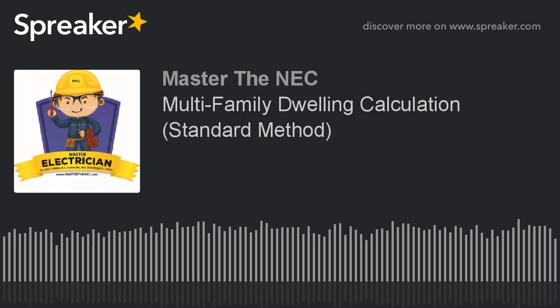So that's our demand factor. It's 47% minus 1 for every dryer that we exceed 11, and we exceeded 11 by 7. You get where we're at now. So basically that's 7%. We take 7% away from the 47% baseline, and that means it's 40%. So when we go back to our calculation, we're going to do 5 kW times 18, because there's 18 of them, times 40%, because that is the demand factor we're allowed to apply in accordance with table 220.54. That's going to result in 36,000 VA.